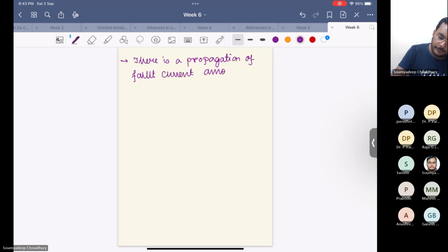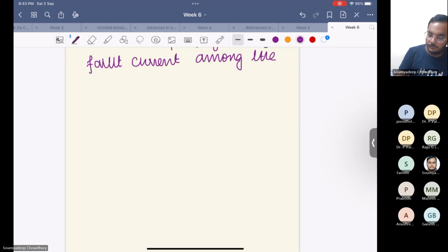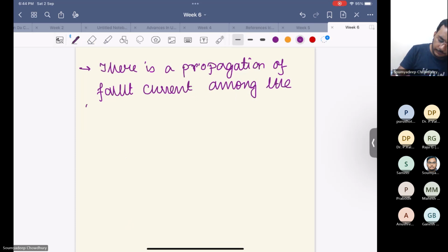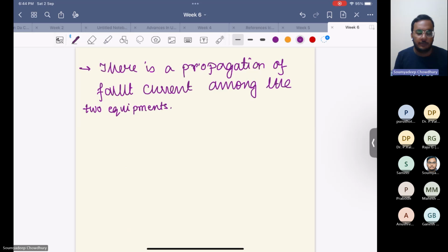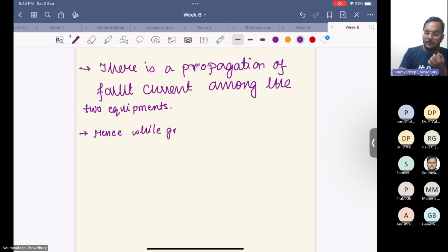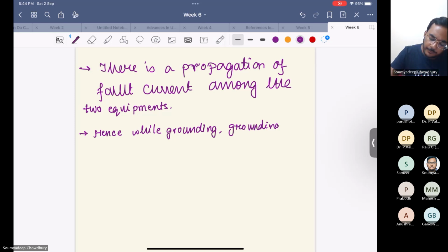So thus we can say that effectively there is a propagation of fault current among the two equipments. So the general advice given to the linesmen or the line engineers in the substations, while grounding, is that you should try to avoid these grounding loops. So grounding loops must be avoided.